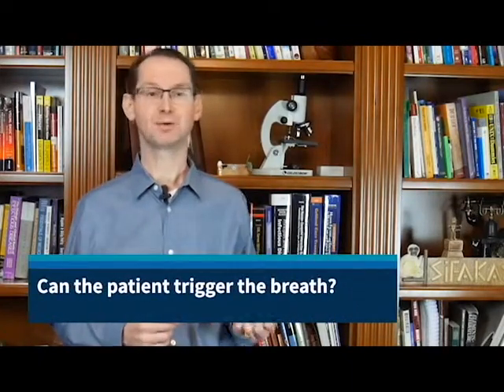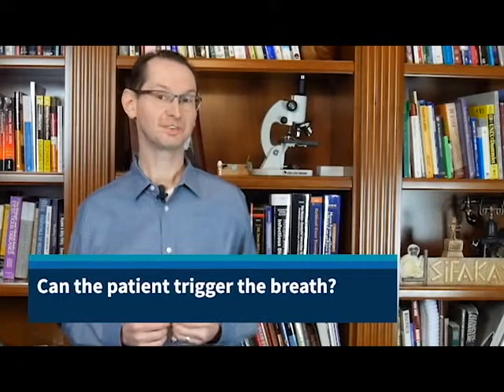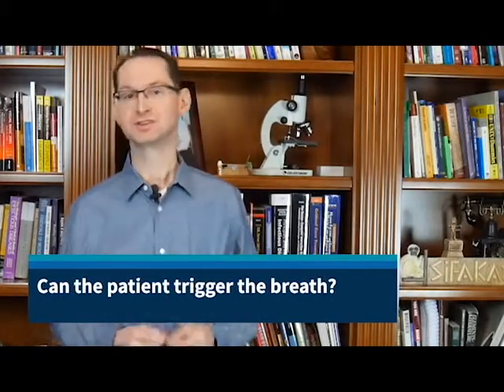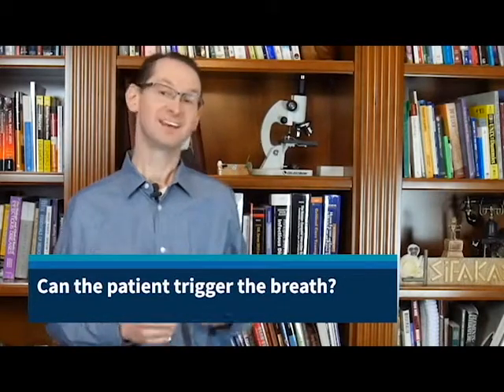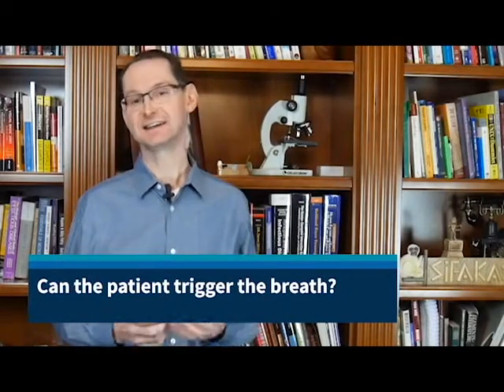You're going to hear a lot of different acronyms for the modes or type of ventilation being used and this can get pretty confusing. So just focus on the following three points. Number one, can the patient start turning on the air pump to deliver breath or is it only the timer? This is what we refer to as the trigger. When the patient can trigger the ventilator to start the breath then the ventilator is set in an assist mode.